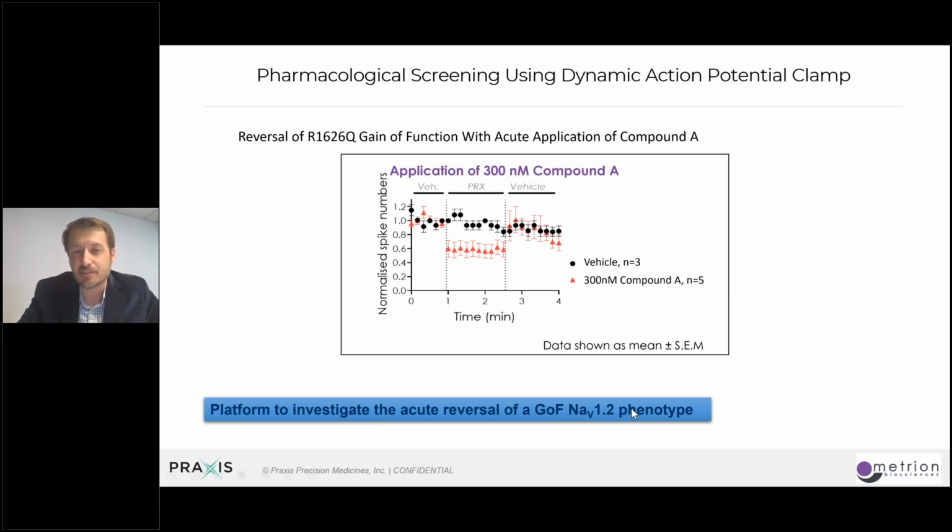It's currently limited based on the ability to get a stable recording configuration. It takes a high degree of technical expertise because you need low noise recordings. And also, this is on a manual patch clamp rig. So the attribute is that you can finally control the bath perfusion. You have an inexhaustible supply of flow through. So unlike many of the systems, you don't have a waste reservoir that is limited. But it is limited in terms of throughput, which is something that is solvable.